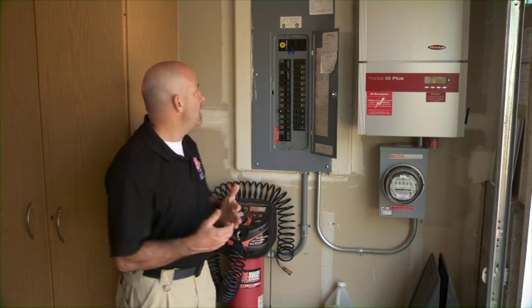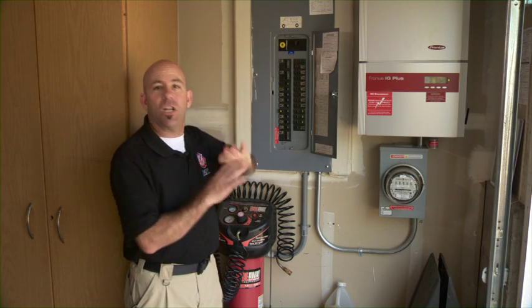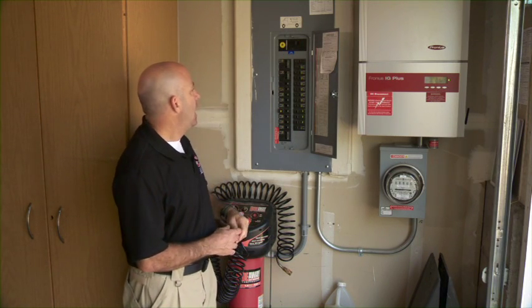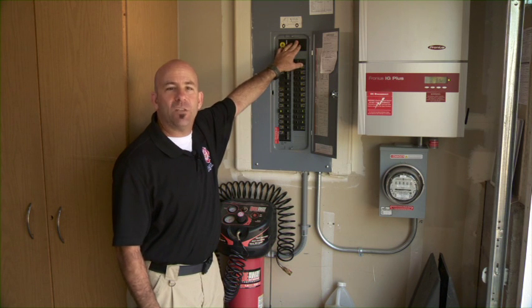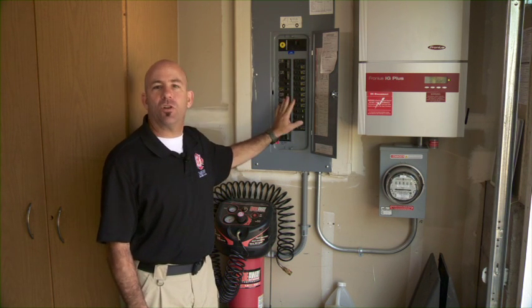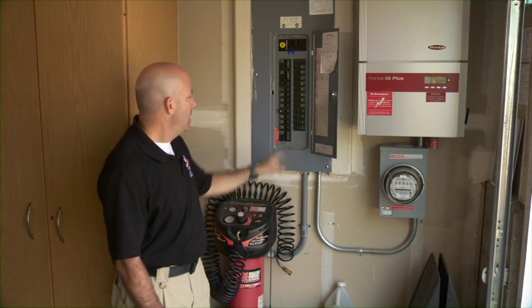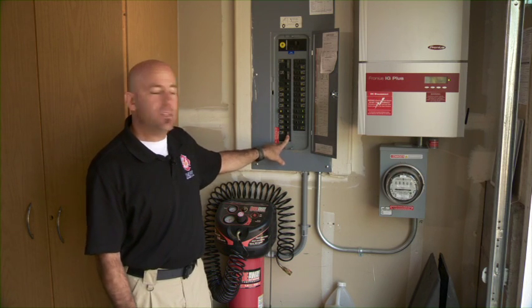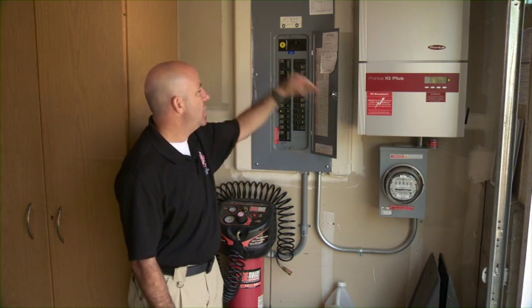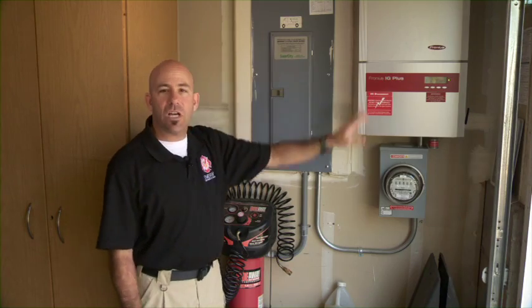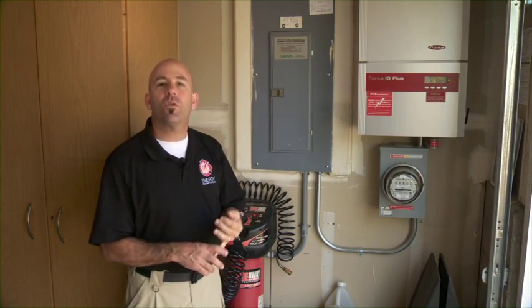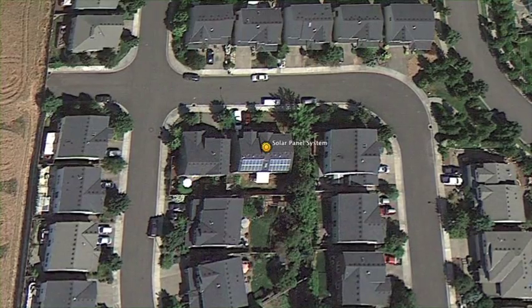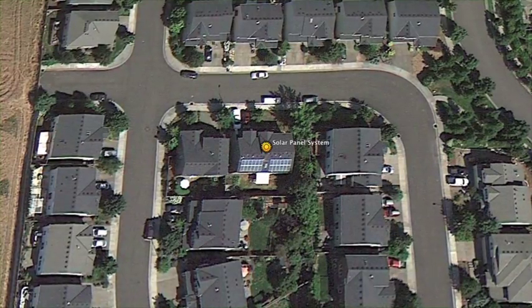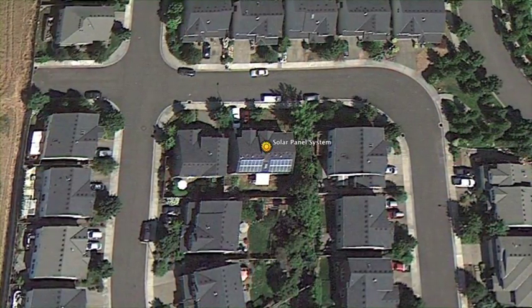In securing utilities, we're going to go after the main. We want to shut off everything. Just remember, shutting off the main is better than turning off all of these individual breakers, preserving any evidence if you had a tripped breaker. But here is the one breaker that shuts off the inverter. So again, we shut off the main, the inverter goes off. There's no power from here into the house, and all the power inside the house is off. Still power up on the roof.